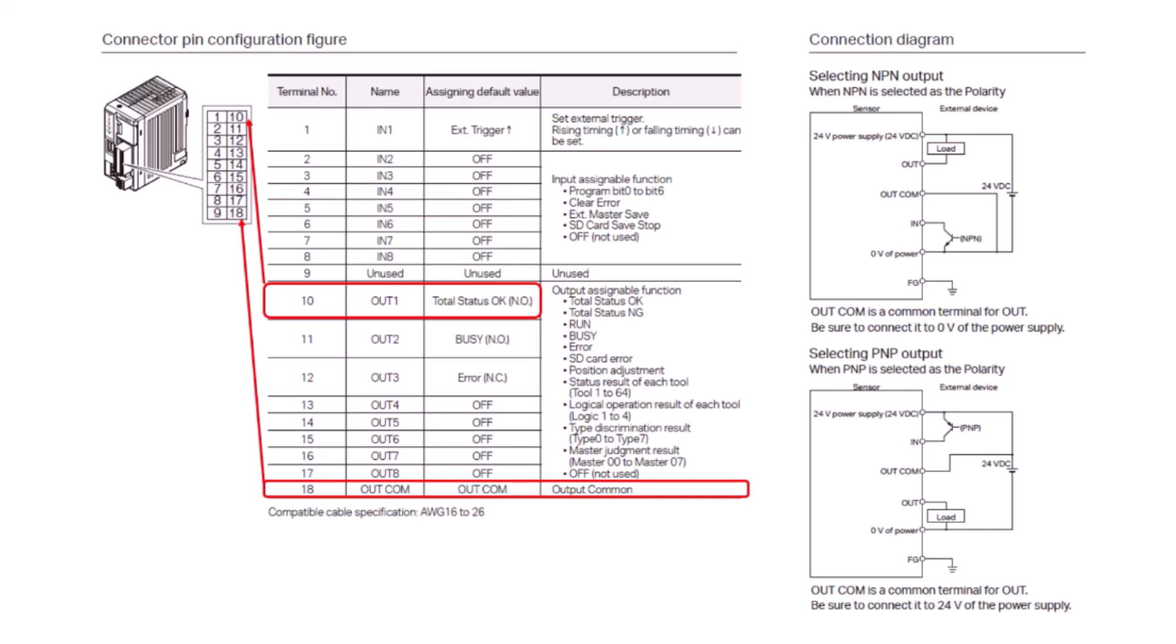It's important to note that the output common is required in order for your other outputs to work correctly. So if you're having any issues with not getting an output signal, be sure to check terminal number 18 for your output common wire.